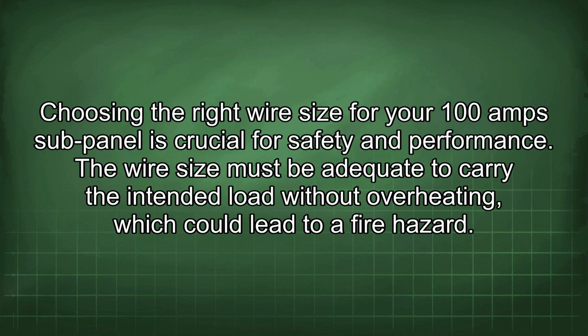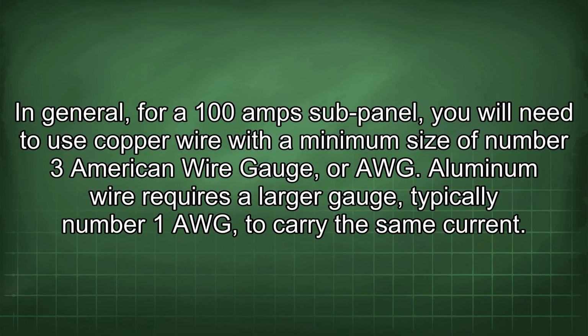Choosing the right wire size for your 100 amp sub-panel is crucial for safety and performance. The wire size must be adequate to carry the intended load without overheating, which could lead to a fire hazard. In general, for a 100 amp sub-panel, you will need to use copper wire with a minimum size of number 3 American Wire Gauge, or AWG. Aluminum wire requires a larger gauge, typically number 1 AWG, to carry the same current.